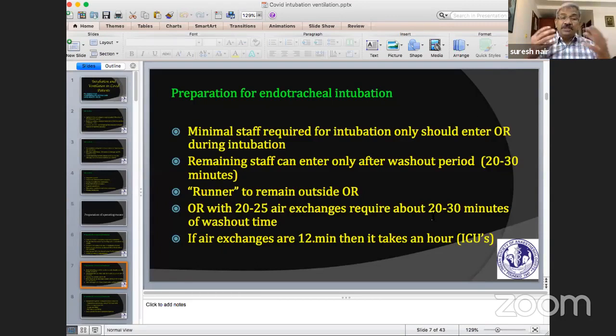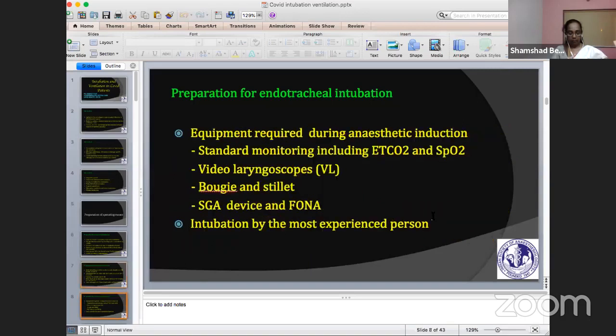So you intubate the patient after 20 minutes, during which we can utilize the time for putting in lines or giving blocks. Then the rest of the team comes in and starts preparing the equipment. On the other hand, if the exchanges are much less, for example only 12 air exchanges per minute, that means we have to wait for an hour before the rest of the team can come inside.